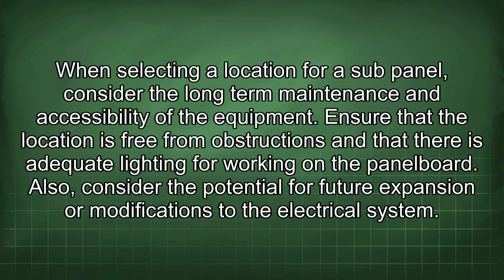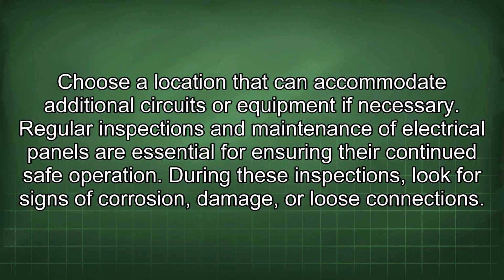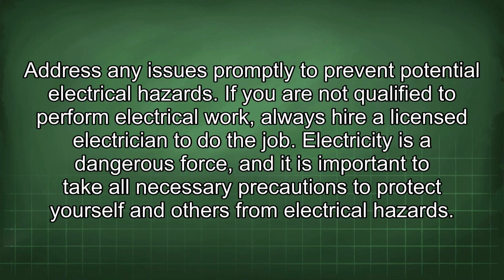When selecting a location for a sub-panel, consider the long-term maintenance and accessibility of the equipment. Ensure that the location is free from obstructions and that there is adequate lighting for working on the panel board. Also, consider the potential for future expansion or modifications to the electrical system. Choose a location that can accommodate additional circuits or equipment if necessary. Regular inspections and maintenance of electrical panels are essential for ensuring their continued safe operation. During these inspections, look for signs of corrosion, damage, or loose connections. Address any issues promptly to prevent potential electrical hazards.